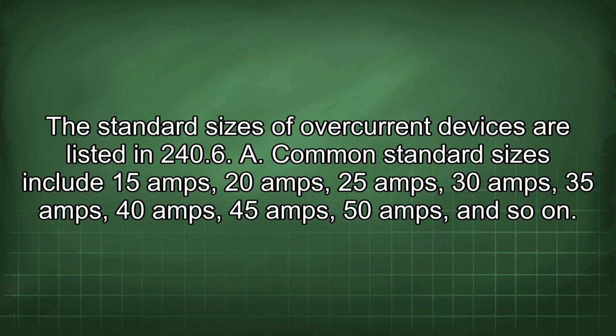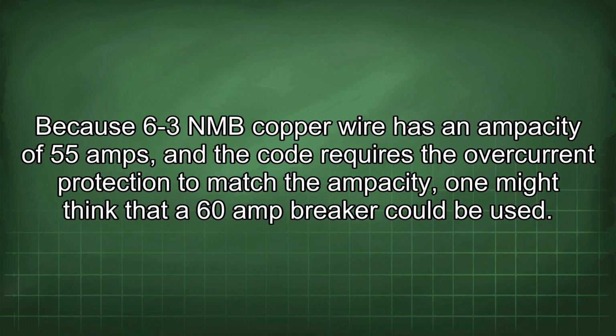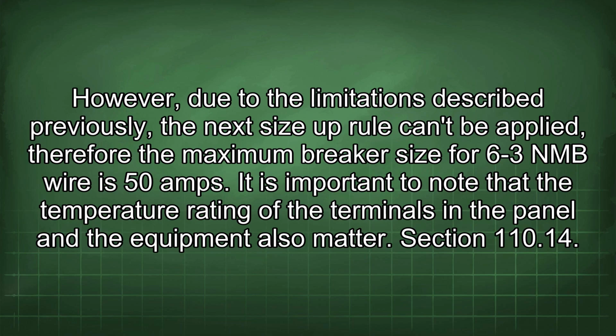The standard sizes of overcurrent devices are listed in 240.6(A). Common standard sizes include 15 amps, 20 amps, 25 amps, 30 amps, 35 amps, 40 amps, 45 amps, 50 amps, and so on. Because 6-3 NMB copper wire has an ampacity of 55 amps, and the code requires the overcurrent protection to match the ampacity, one might think that a 60 amp breaker could be used. However, due to the limitations described previously, the next size up rule can't be applied. Therefore, the maximum breaker size for 6-3 NMB wire is 50 amps.